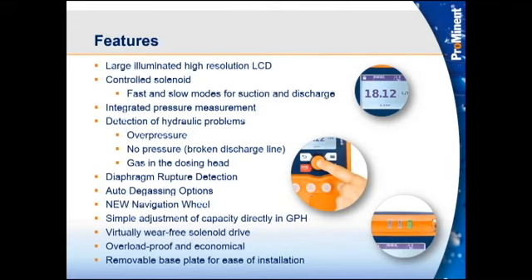So typically, if you're familiar with our pumps, they have kind of the ear tabs sticking off the bottom of the pumps. We've gotten rid of that. You'll see it in further slides. There's now a base plate that slides into the bottom of the pump. That base plate has numerous mounting holes on it, and those mounting holes are the same pattern as a Gamma L pump. Okay, so if somebody has a pump stand and they have the holes already for the Gamma L, they can slide this pump right in there.